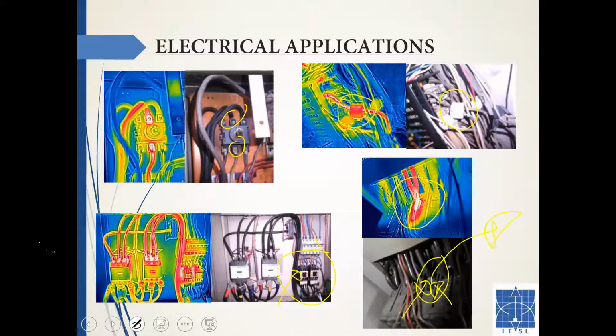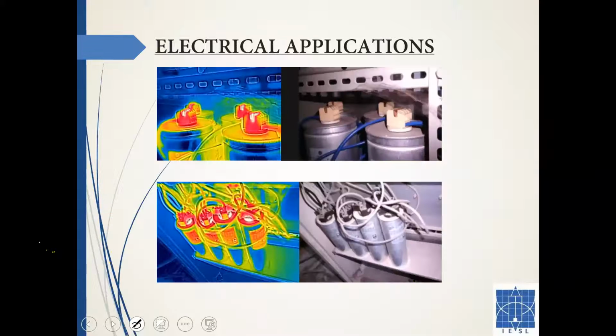So these are some electrical applications, some images I have captured during service. And oh yeah, this is my favorite. These capacitors, every time we see them, these capacitors, they are overheated. So I have been looking into this in detail and found that there are some inherent attributes, the design of these capacitors. So mostly the clients, they don't maintain these capacitors. There is a limit to the ambient temperature. So you can see some cobwebs right here, right? So that tells the amount of maintenance that goes into the capacitor bank maintenance.